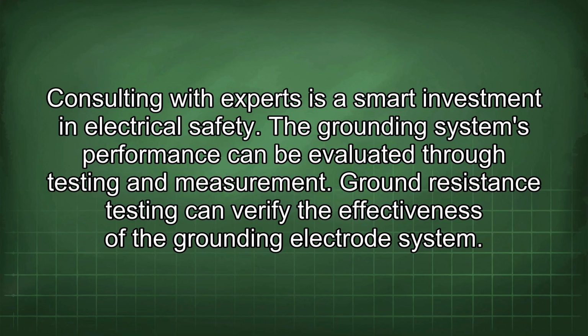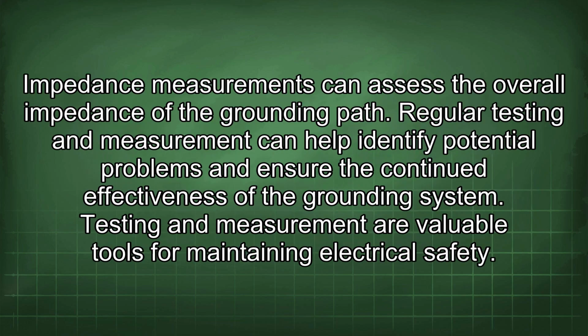The grounding system's performance can be evaluated through testing and measurement. Ground resistance testing can verify the effectiveness of the grounding electrode system. Impedance measurements can assess the overall impedance of the grounding path. Regular testing and measurement can help identify potential problems and ensure the continued effectiveness of the grounding system. Testing and measurement are valuable tools for maintaining electrical safety.